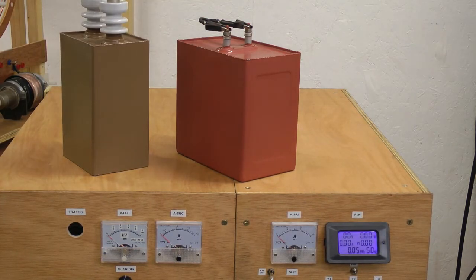That's why you also need a discharge unit. If your valve stops, or your experimental work stops for some reason, the valve stops oscillating, that capacitor bank can be left with an enormous amount of energy on it. And before you can get anywhere into that circuit or make modifications or try something else out, you need to safely discharge that capacitor. That's what the internal discharge circuit is all about.